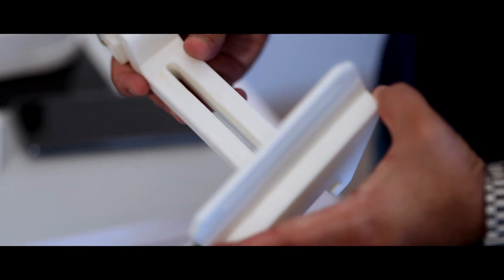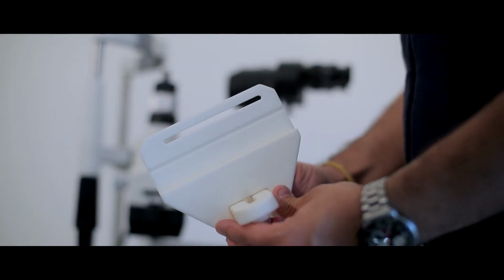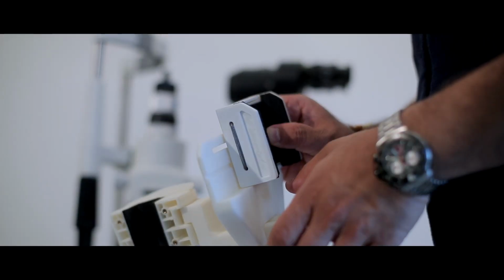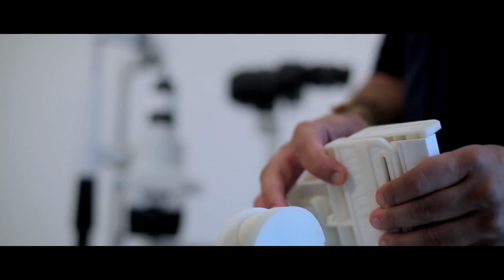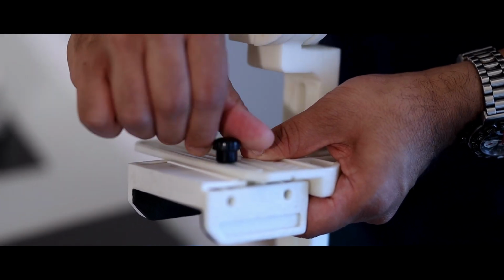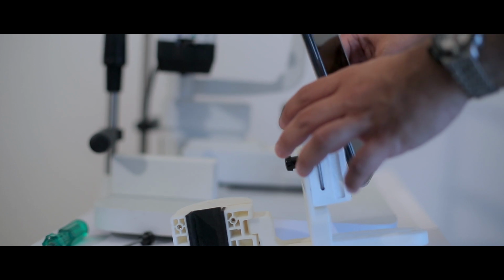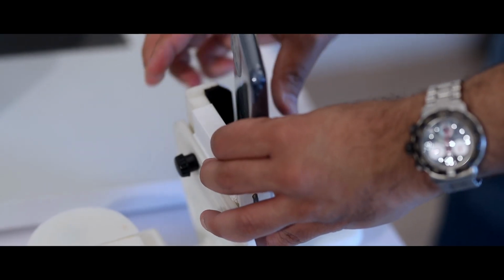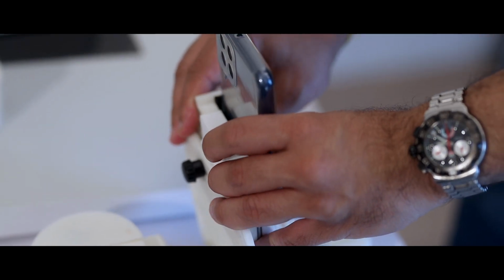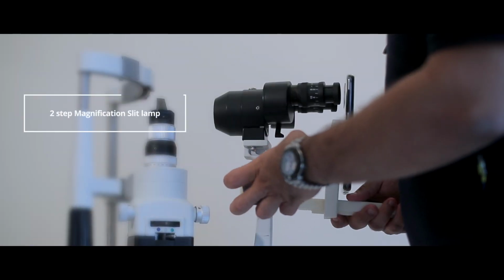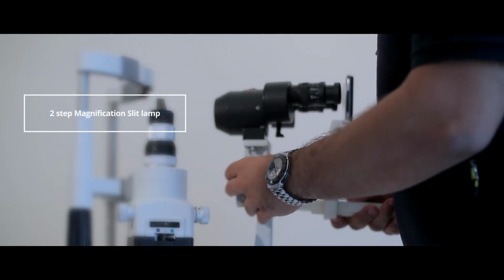Slide the base of the adapter onto the rotating arm. Attach the smartphone holder onto the base and lock it in position using the knob. Attach the smartphone onto the smartphone holder. You can use any smartphone with the device. The device is compatible with the majority of slit lamps.